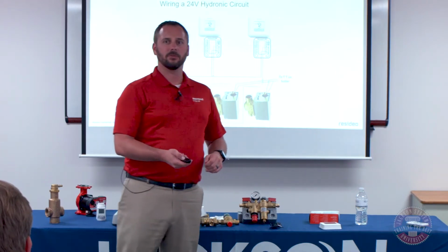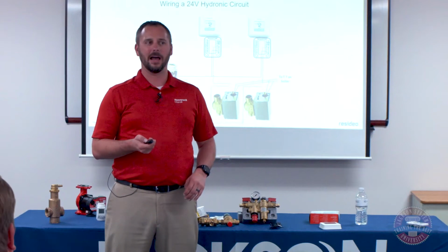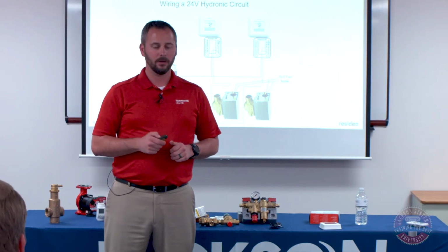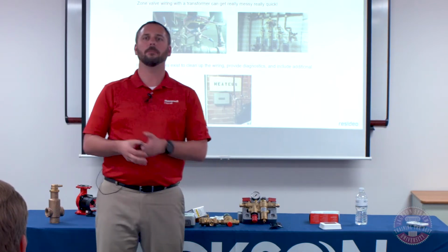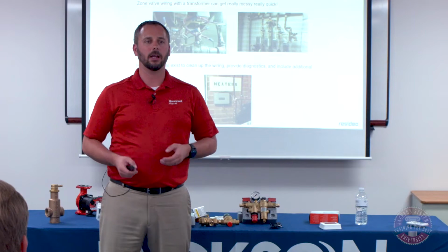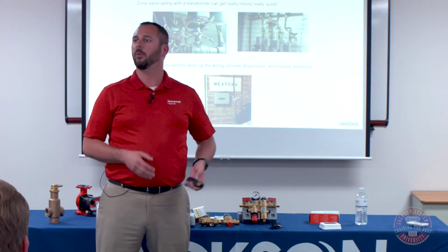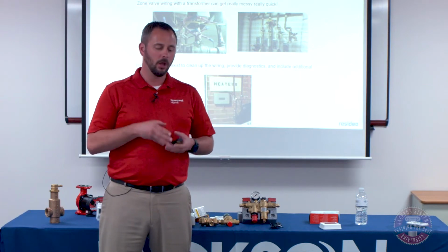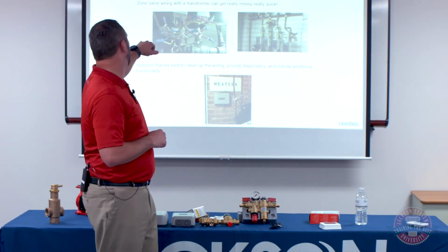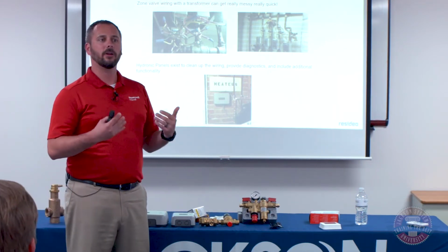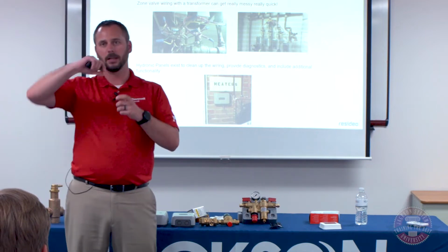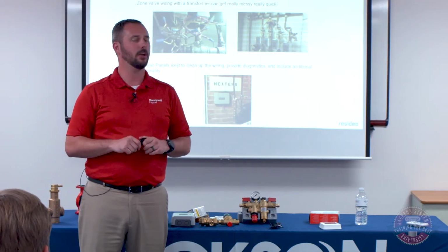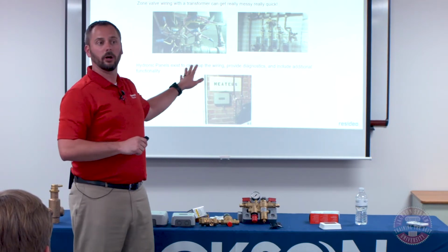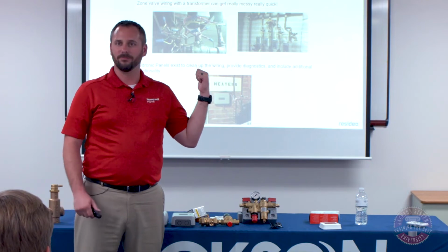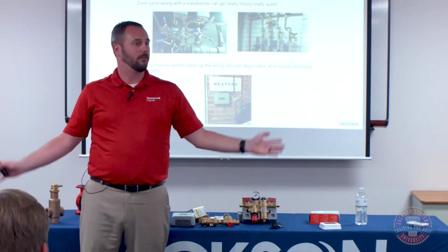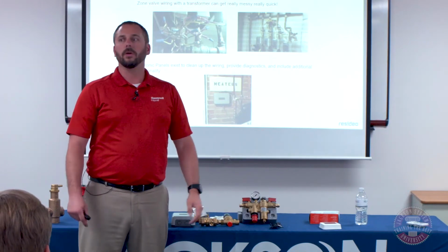So we sell a lot of thermostats, got lots of different capacities, sell lots of zone valves. There is nothing wrong with doing it this way. However, I've been on a lot of job sites, and in my previous life, I got called out typically when nobody could figure out what was going on with the wiring and why the boiler wasn't working and why the valves weren't opening. I've seen everything from a wire nest like we see on the left to what looks like a very professional install on the top right, where everybody twisted all the wires together but then jammed them inside a junction box. That is incredibly difficult. While it will work if it was wired properly, that is a nightmare to troubleshoot. I have walked in on a lot and said, I'm not even getting my voltmeter out. Let's just cut it all and start over. So it's very time consuming.